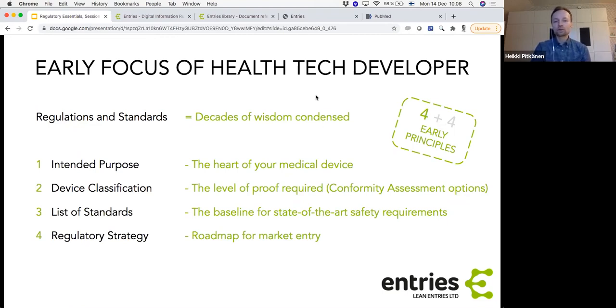Then the first 4 principles would be to focus on your intended purpose, and that has a lot to do with clinical evaluation and risk management. Then to define the device classification, to know how much work you have ahead of you, and whether a notified body will need to be involved in your assessment. Then a list of standards to tackle what is considered the state of the art in safety at the current date. And in future, you would need to look at the newly updated standards. And then a sort of regulatory strategy that is also a requirement nowadays in the MDR and the IVDR that will provide you with a roadmap for market entry.